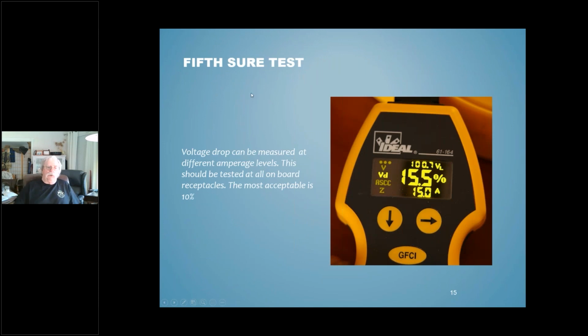Voltage drop is probably one of its greatest strengths as a tool, and it'll measure at I think 3 points, as I recall: 10 amps, 15 amps, and 20 amps. You don't want to see any more than 10% voltage drop from the norm. And what's indicated here, and it'll measure for both the hot, neutral, and ground, is either a bad connection or wiring that's undersized. And that's what we're trying to determine.